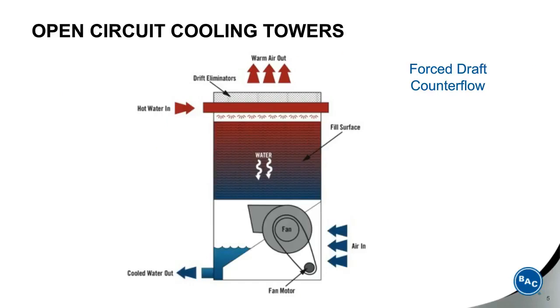A forced draft counterflow cooling tower, which in this instance has a centrifugal fan. The air is blown up through the fill pack, and the hot water is sprayed down over the fill, where again the air and water mix to be cooled. This type of cooling tower is often used for indoor applications in cold weather areas or in high security installations, or for sound sensitive sites.